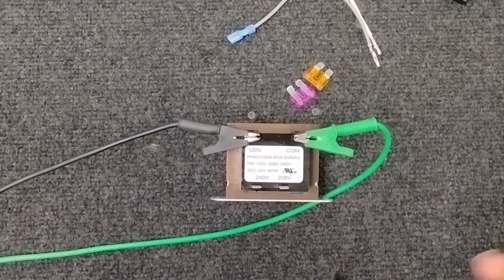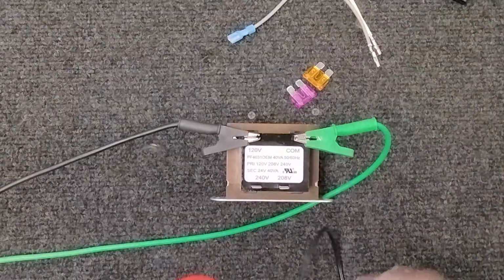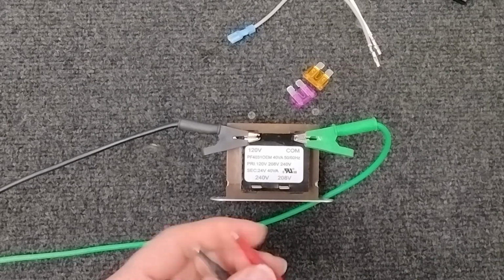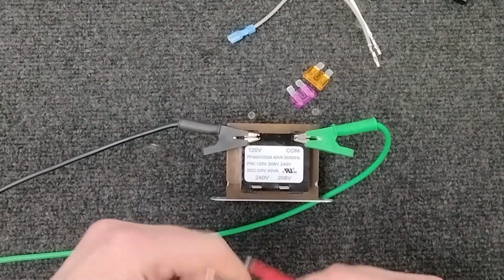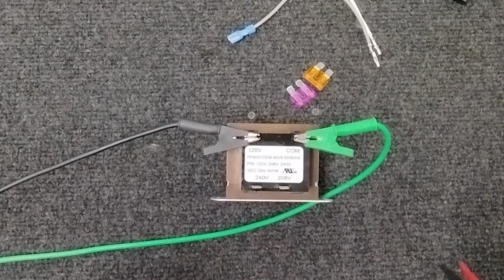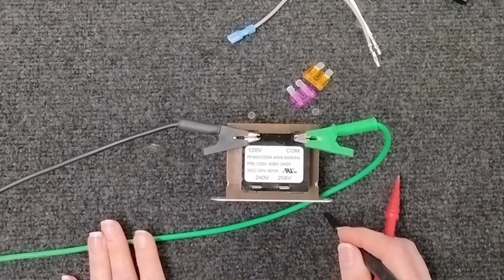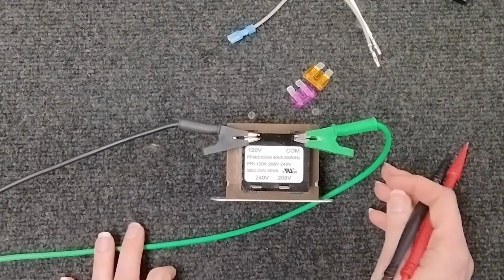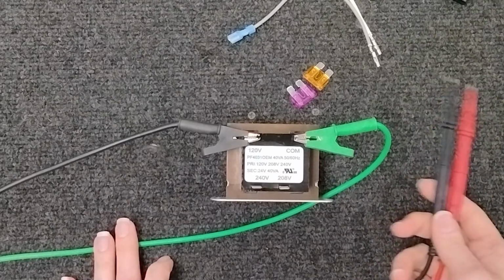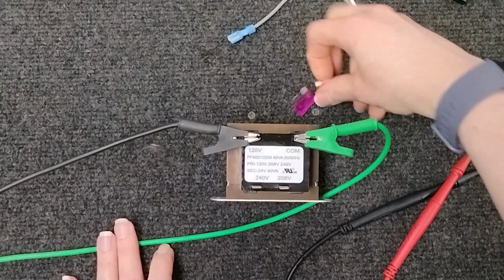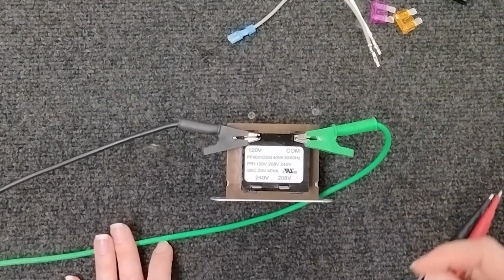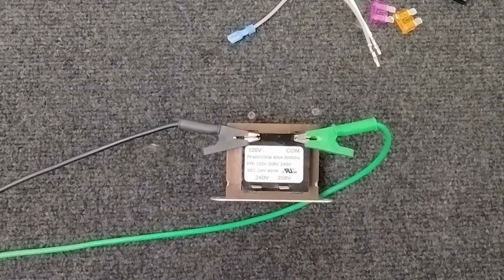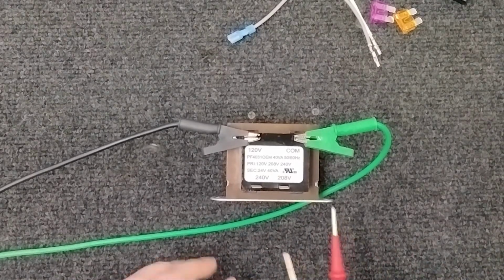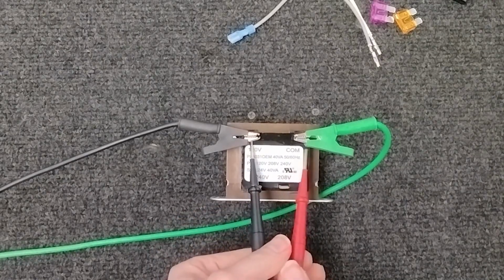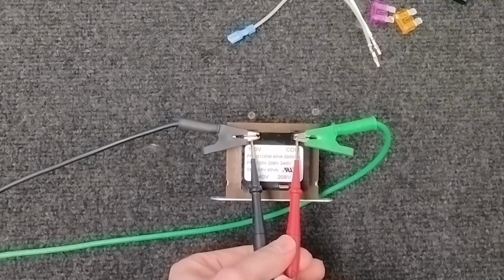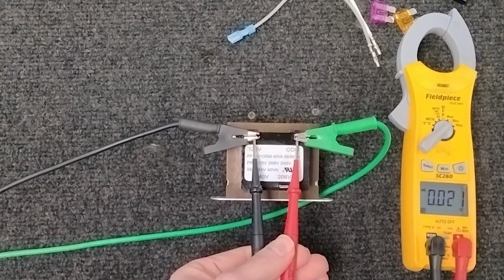So with our meter set to volts AC, we are then going to turn the call for heat or cool on, depending on which you're trying to attempt here, because this is the power for everything on your inside unit and your outside unit, unless, of course, some of you do have a transformer on outside units, or package units can be on a rooftop, and it's going to be a little different. So now we're going to check and make sure we are getting our voltage first and foremost, just so you don't waste your time having to go through checking everything without realizing that you might not have power.